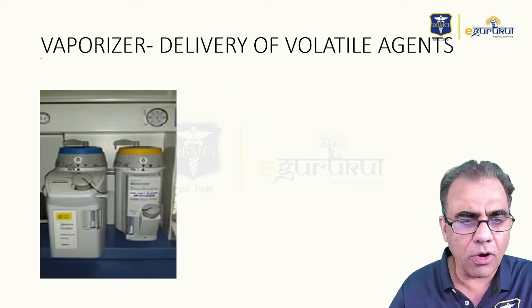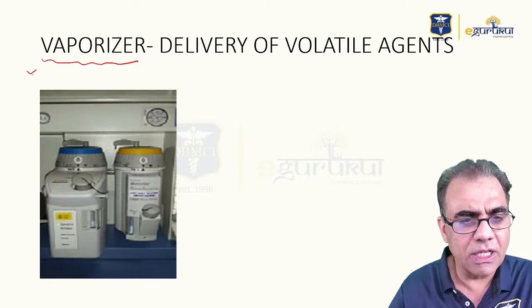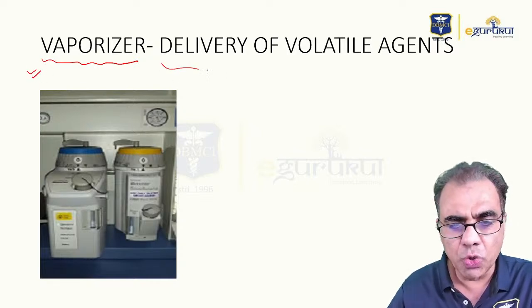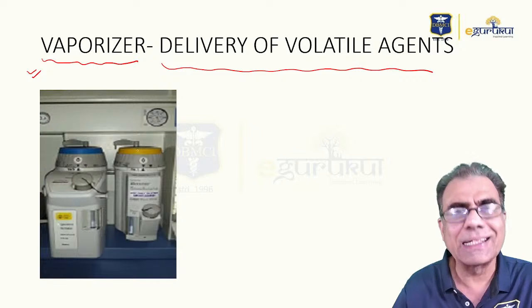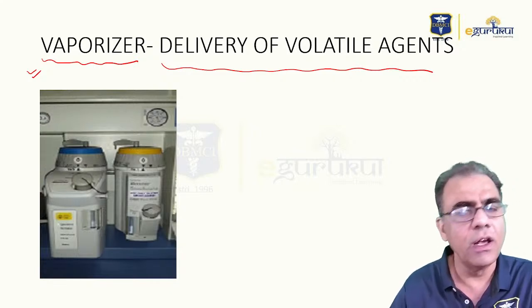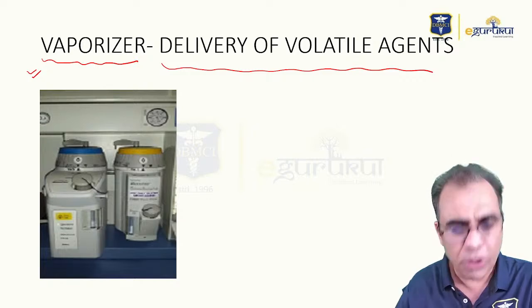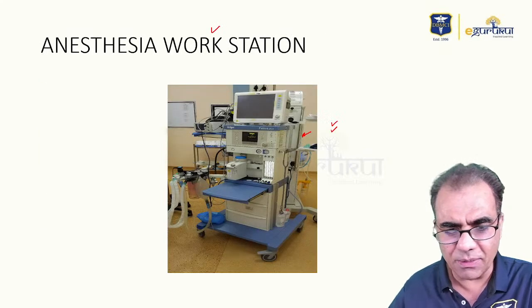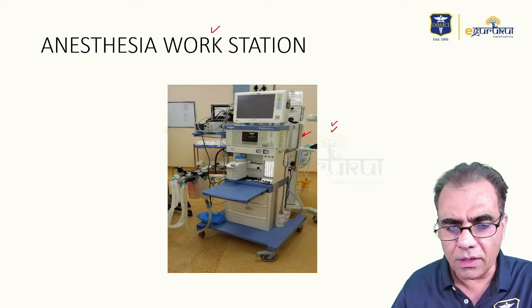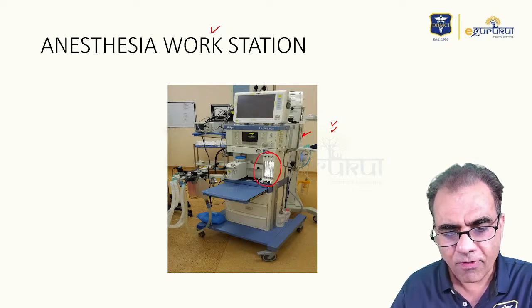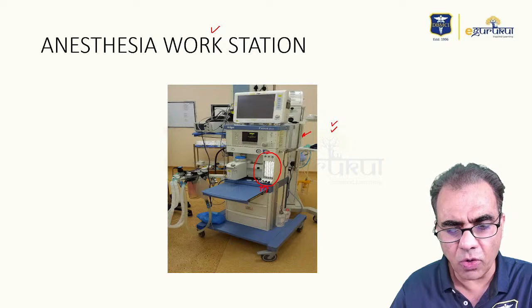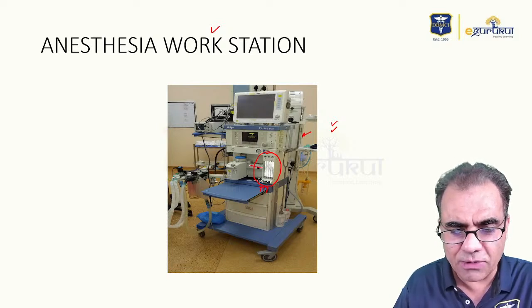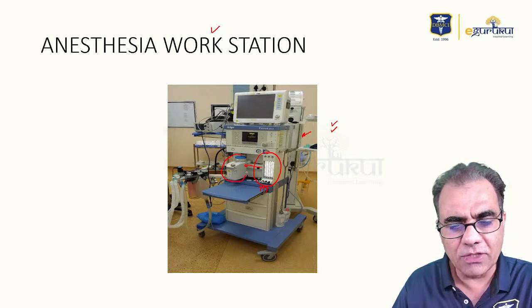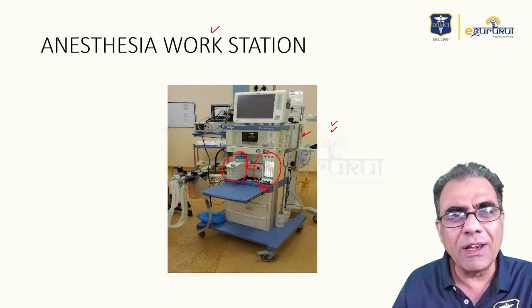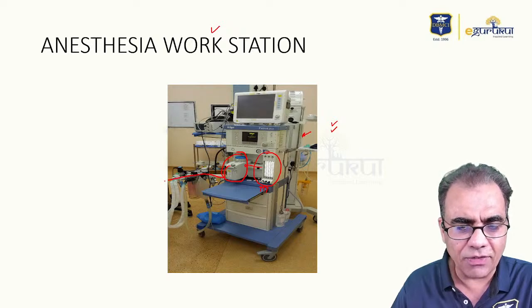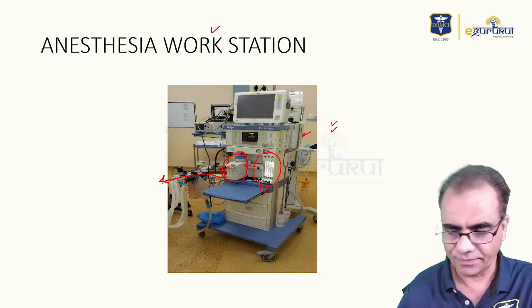Another very important component of the anesthesia machine is the vaporizer. The vaporizer is used for the delivery of volatile agents, which may be halothane, isoflurane, desflurane, sevoflurane, whatever you are using. So now we can look at the anesthesia machine. You can see this is the rotameter where you can set the flow rates, how much you want to give. After that, these gases will pass through this vaporizer, which contains the volatile agent. So the volatile agent will mix with this gas mixture, and that can be delivered to the patient.